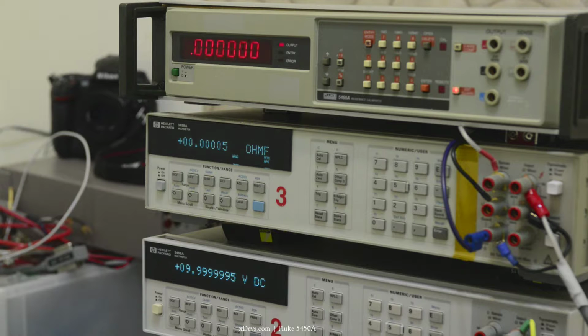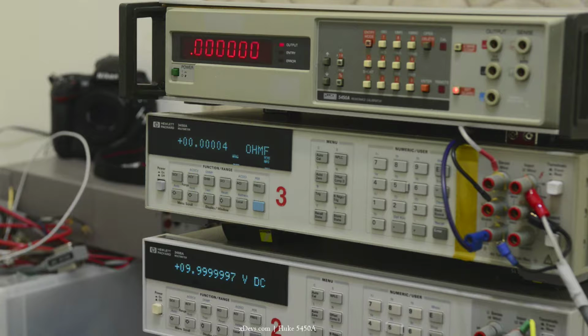The 5450A doesn't measure anything itself, it just shows on display the actual calibrated value of the specific resistor. Essentially it's just a box with relays and different precision resistors made by Fluke. Those are wire-wound type, hermetically sealed, so they're very stable over time. Even today this box is very useful for checking various DMMs, and it's capable of calibrating even meters up to 6.5 digits.